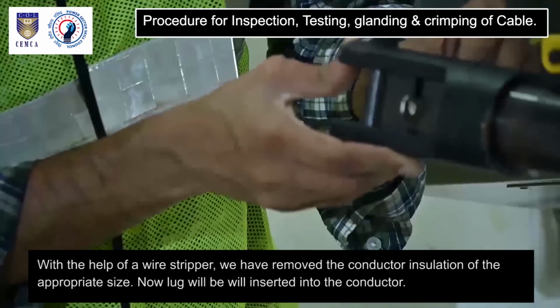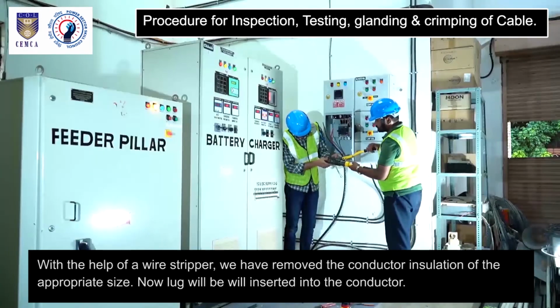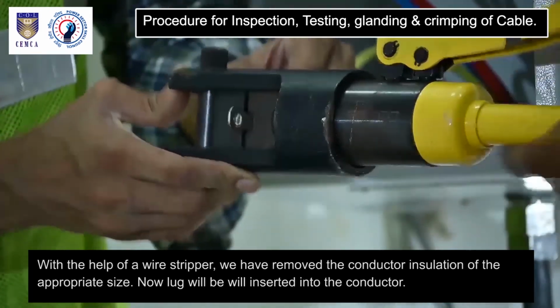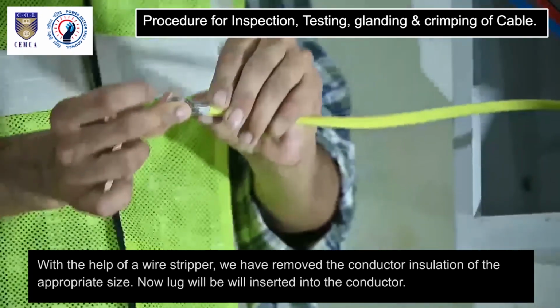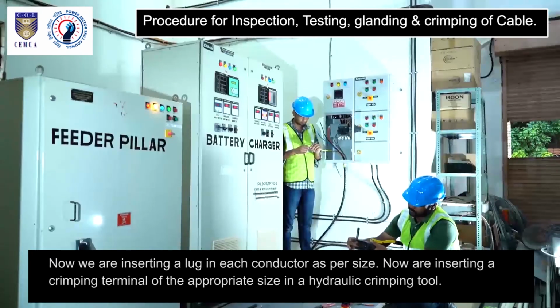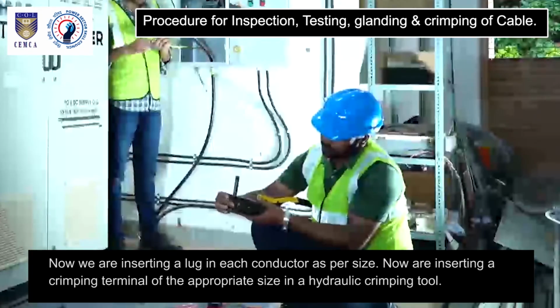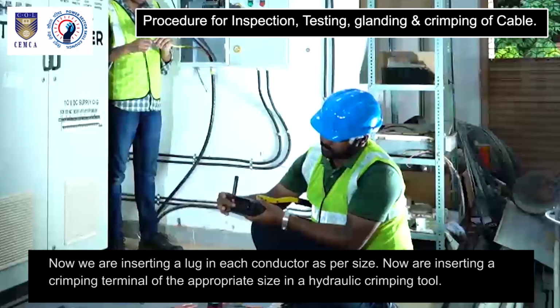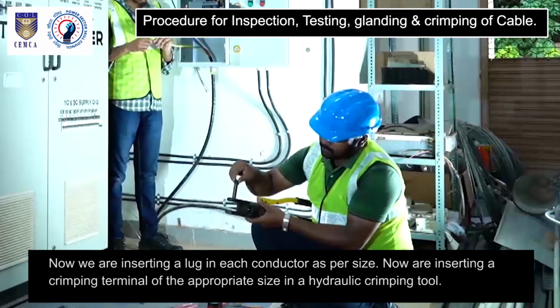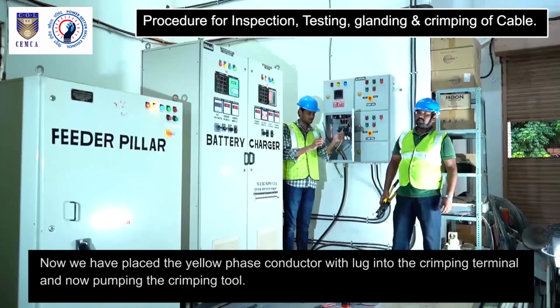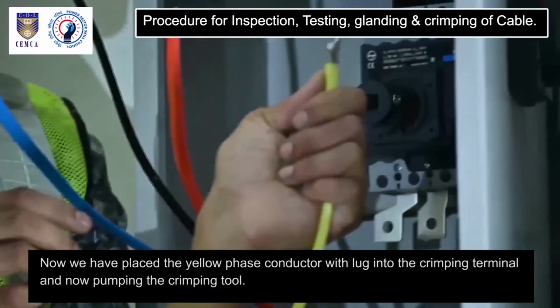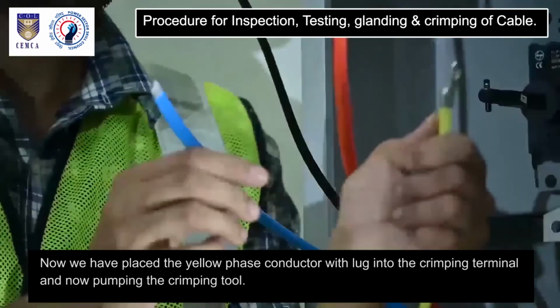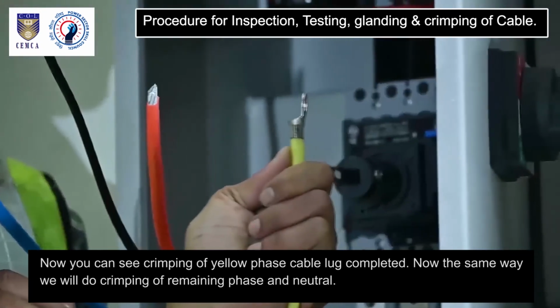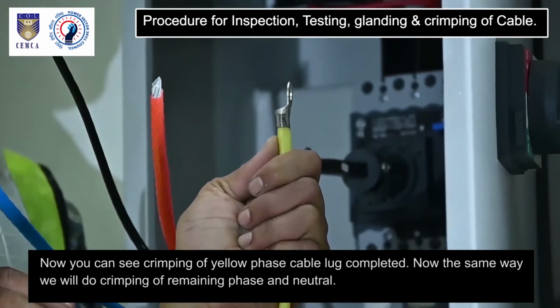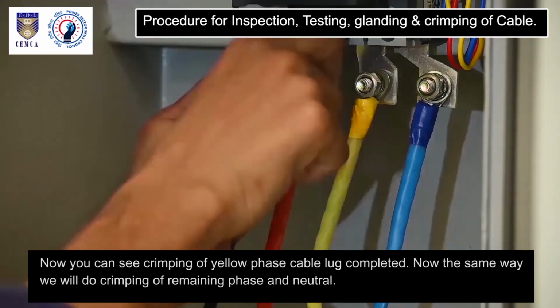With the help of a wire stripper, we have removed the conductor insulation of the appropriate size. Now lug will be inserted into the conductor. Now we are inserting a lug in each conductor as per size. Now we are inserting a crimping terminal of the appropriate size in a hydraulic crimping tool. Now we have placed the yellow phase conductor with lug into the crimping terminal and now pumping the crimping tool. Now you can see crimping of yellow phase cable lug completed. Now the same way we will do crimping of remaining phase and neutral.